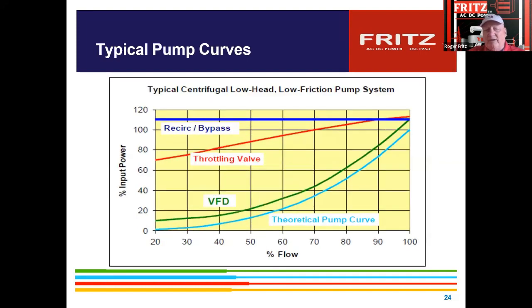And then this is more of a typical pump curve with a VFD, but it just doesn't show in here. We have software that actually shows where the sweet spot is to run the VFD in, so that when you design it, you set your upper and lower limits so that they stay in that sweet spot of operation.